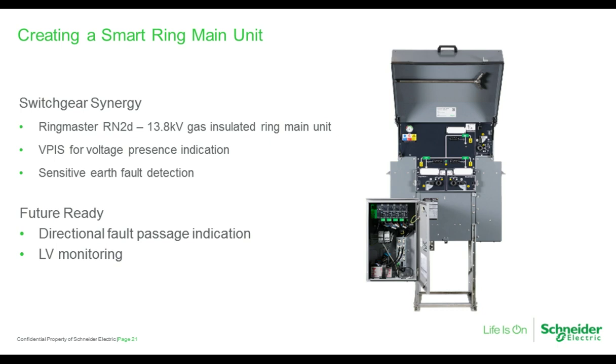In some cases it's actually led to simplification of the process. For example, when we were using previous feeder RTUs, we would be fitting core balance CTs onto ring main units to give us sensitive earth fault detection, whereas T300 has such fine level data reading and management that we can deploy sensitive earth fault detection without using core balance CTs.